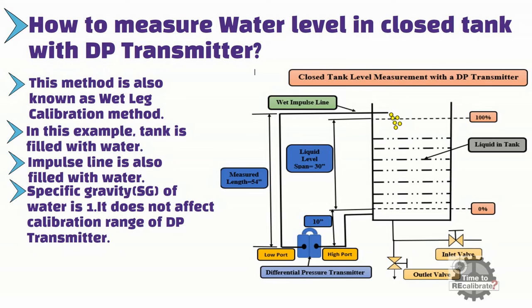In this example, the differential pressure transmitter is located 10 inches below the zero percent baseline. One end of the tube is connected with the high port of the transmitter and the other end is connected with the tank. This tube is also filled with water and puts pressure on the high side of the transmitter. This is the reason that transmitter position is very important in closed tank level measurement. If you do not measure the distance accurately from the transmitter to the zero percent baseline, you won't be able to measure level accurately.